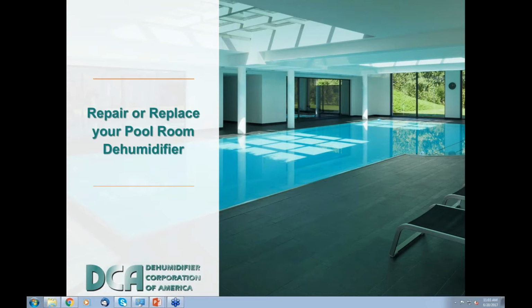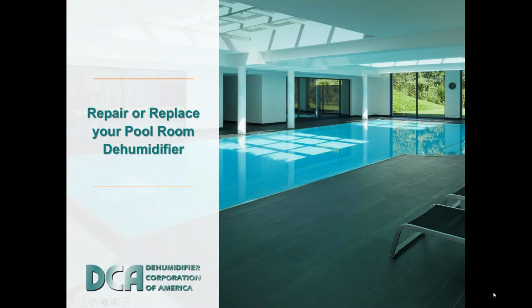So today, we want to cover some of the major points for maintaining and replacing dehumidification units to make sure your system is performing at its best. The major keys here include understanding and recognizing common issues and the problems that can arise if these issues go unaddressed, effectively determining whether to repair or replace a unit, and creating an effective maintenance and monitoring plan to extend the life of your unit. Understanding each of these points is critical to make sure you don't experience serious problems with your unit and your pool room. The last thing anybody needs is to shut down the entire space to repair not only the unit, but likely other areas of the room that would be negatively affected as well.